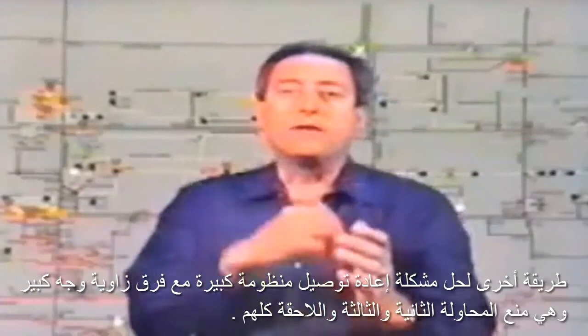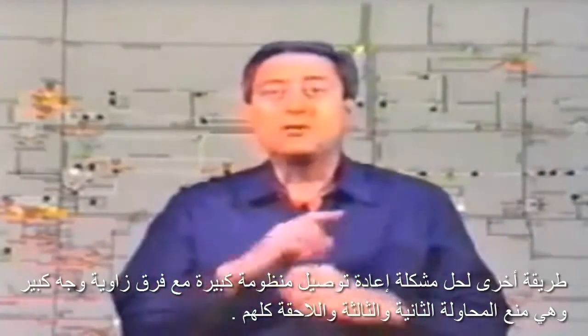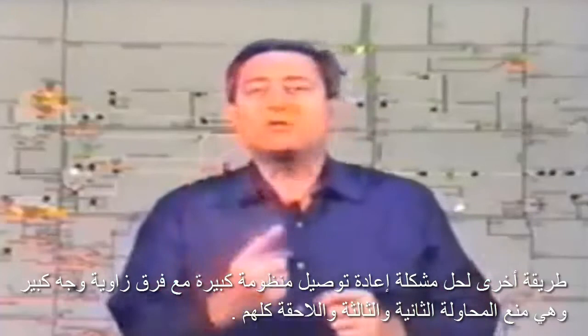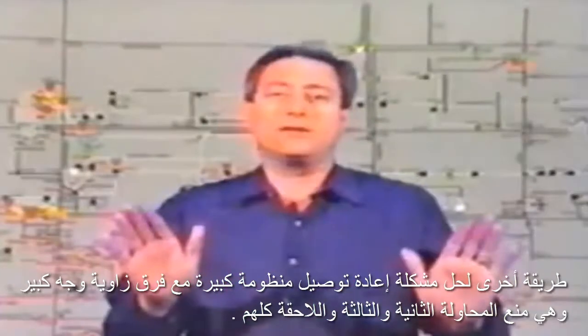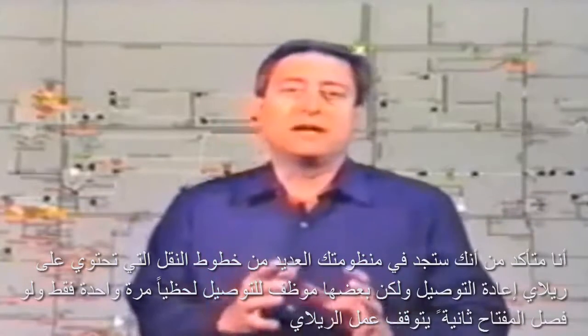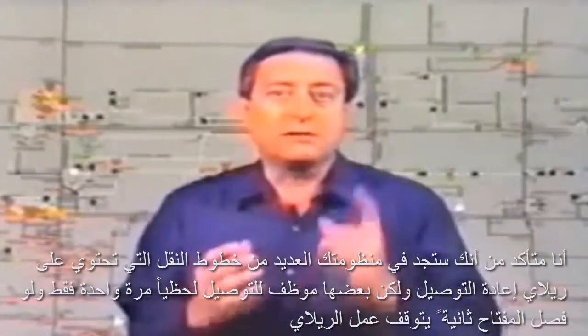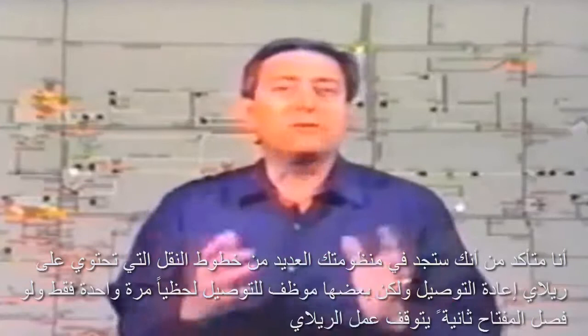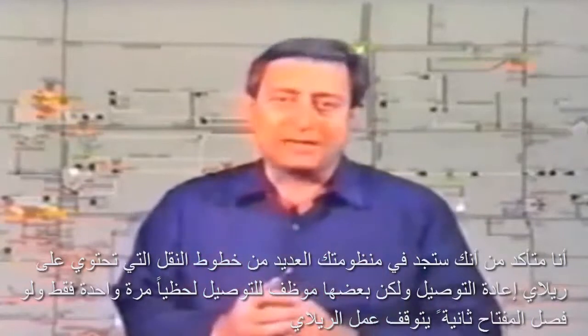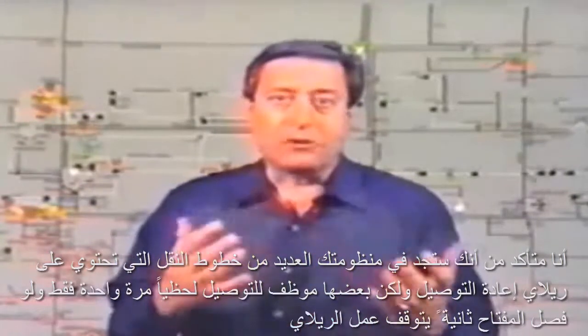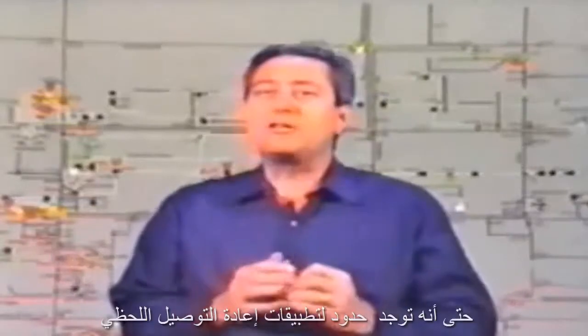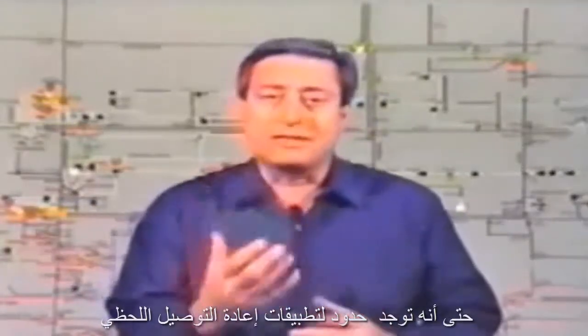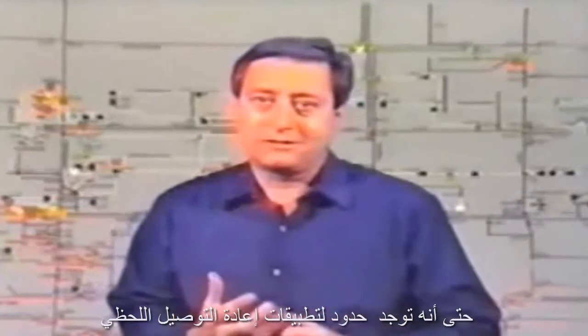Yet another way around this problem of reclosing into a large phase angle difference is to eliminate the second and subsequent reclosing attempts altogether. I am sure that you will find on your system many transmission lines which have reclosing relays, but some of these are limited to only one instantaneous attempt at reclosing. If the breaker trips again, the relay locks out. There are even limitations to the application of the instantaneous reclosing arrangement.